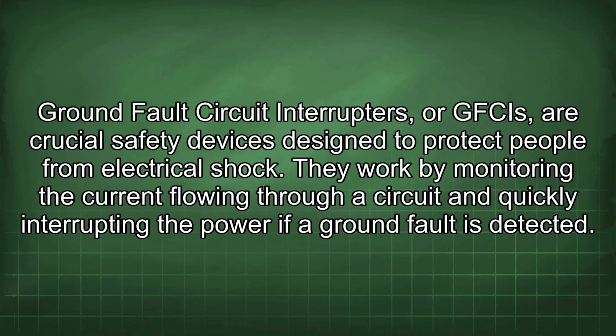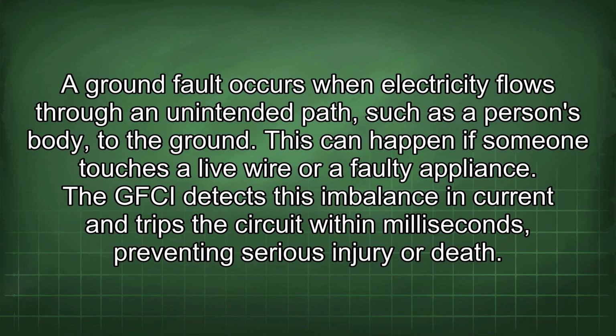Ground fault circuit interrupters, or GFCIs, are crucial safety devices designed to protect people from electrical shock. They work by monitoring the current flowing through a circuit and quickly interrupting the power if a ground fault is detected. A ground fault occurs when electricity flows through an unintended path, such as a person's body, to the ground. This can happen if someone touches a live wire or a faulty appliance. The GFCI detects this imbalance in current and trips the circuit within milliseconds, preventing serious injury or death.